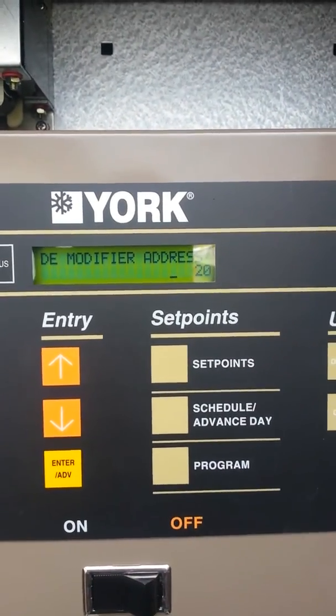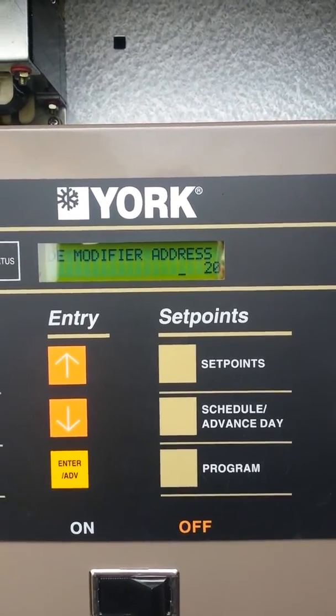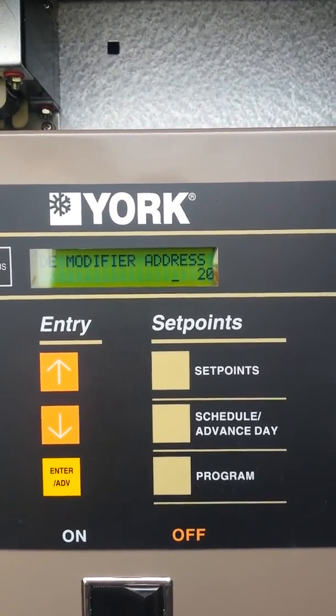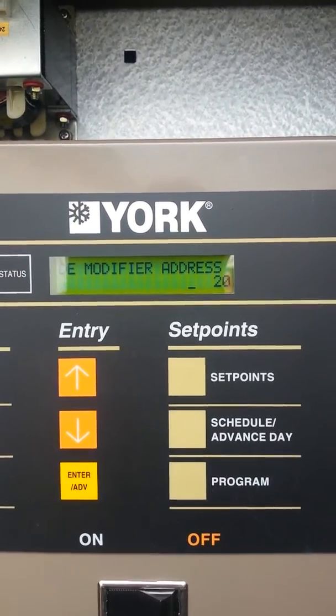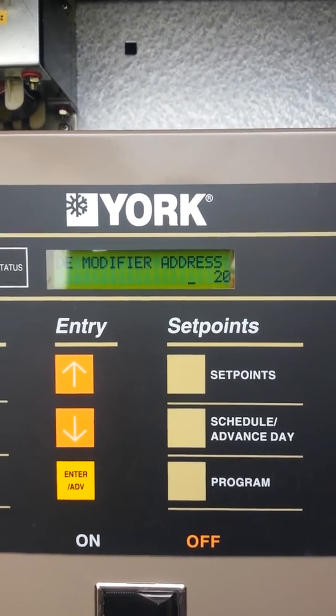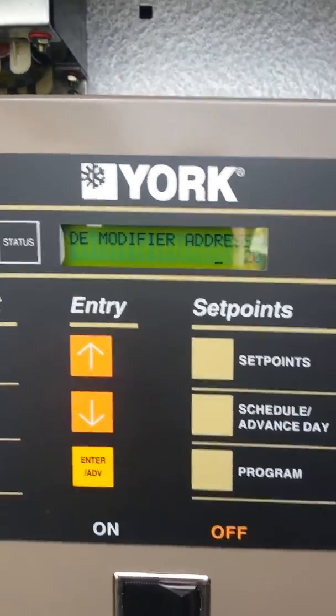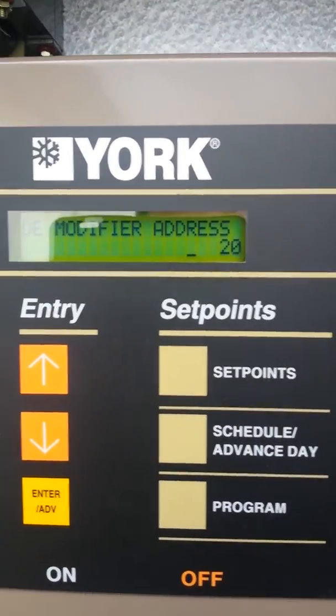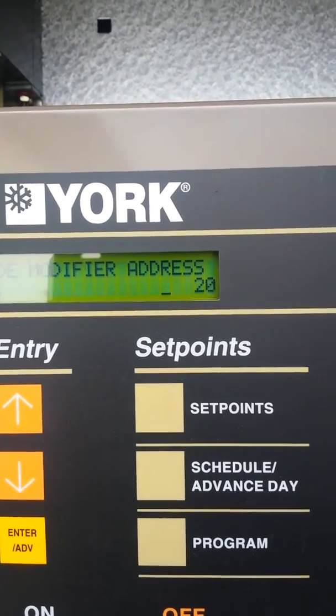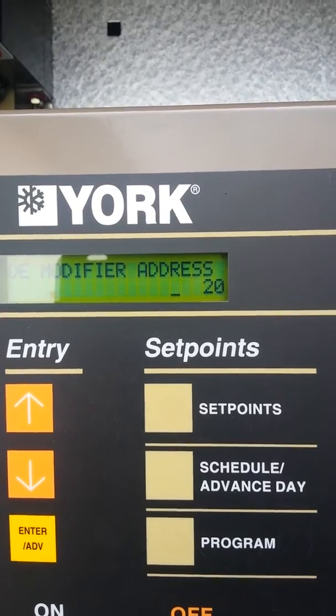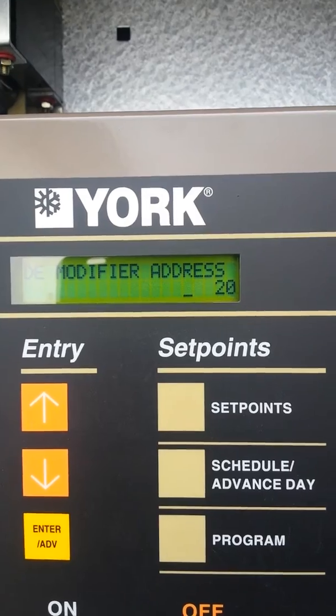And there you are — you're into the BACnet settings. The first one up is the DE modifier address. That's what York calls it, but it is actually the instance number. So if your controls person is asking for the instance number of the device, it's the modifier address number for York. This one is currently set at 20, but each digit where the zero is is times 100 — so even though it says 20, it's actually 2000. This is unit address 2000.